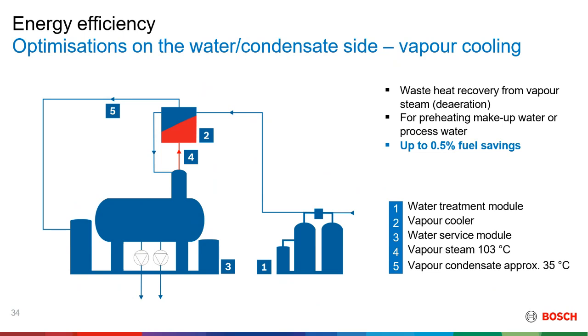Then the other way of saving energy is vapor cooling. During the deaeration process, you will have some flash steam or a bit of steam or hot air leaving the deaerator and flowing into the exhaust. You can save around 0.5% of fuel just by cooling the small vapor leaving the deaerator. You cool this by passing the hot air into a heat exchanger, which also has water from the treatment plant before going into the deaerator.